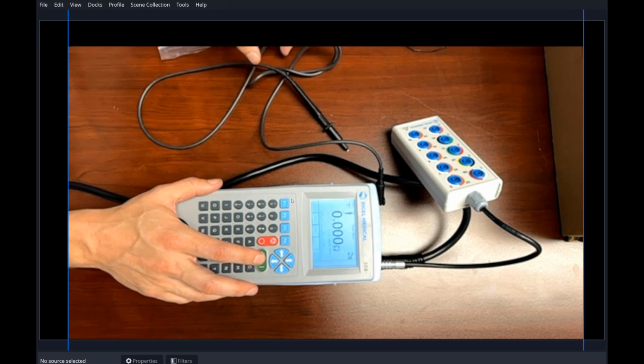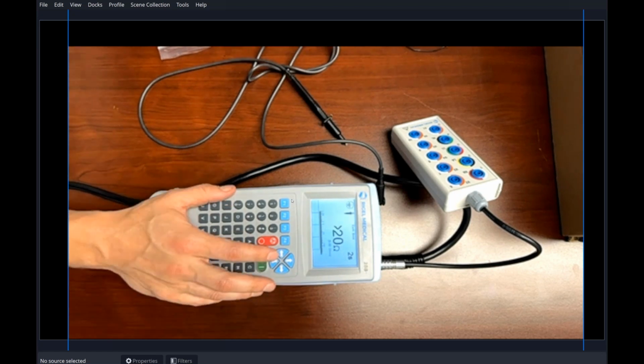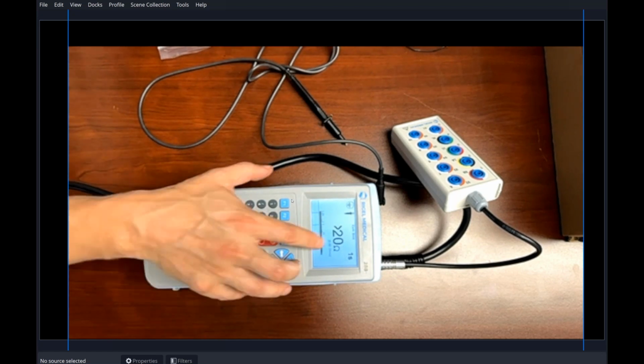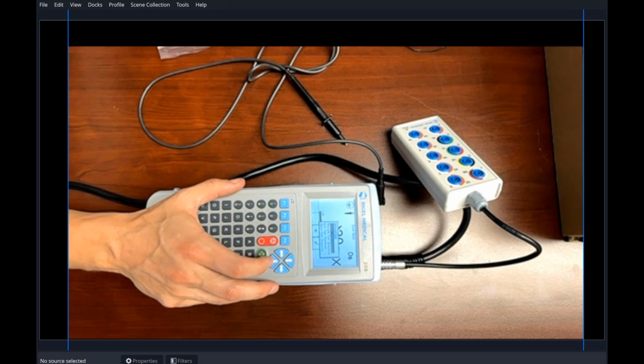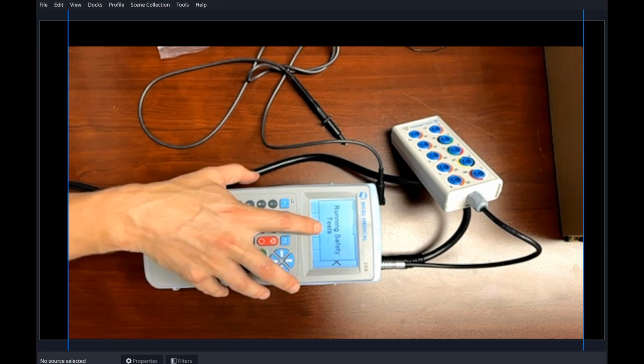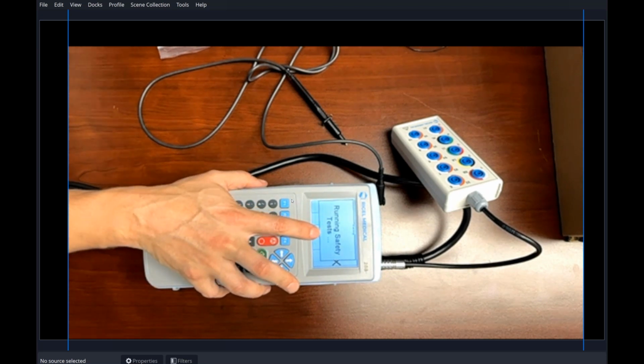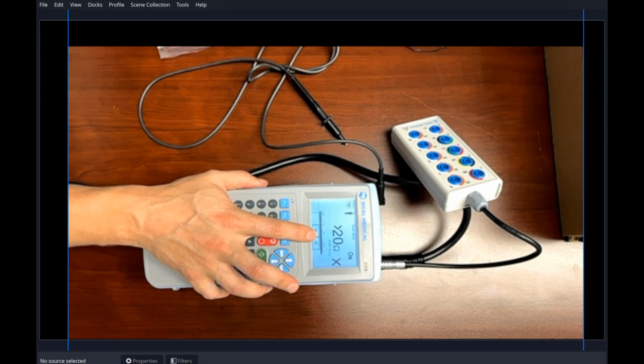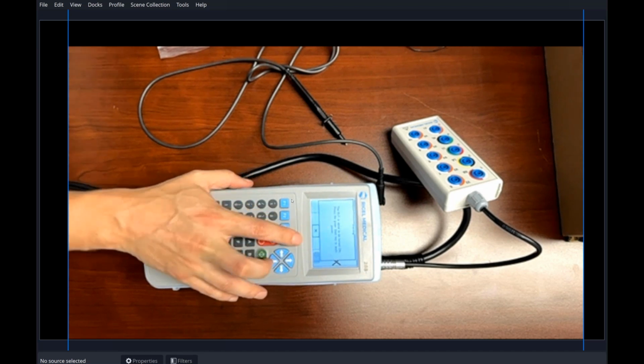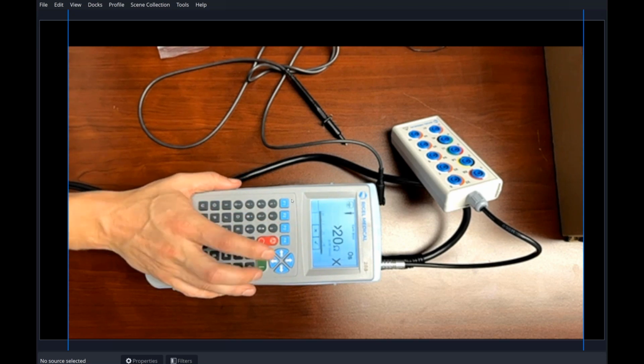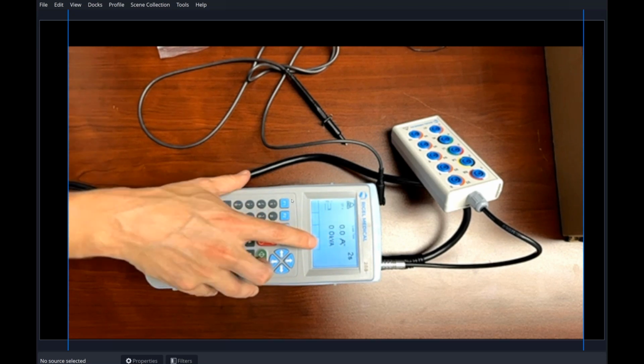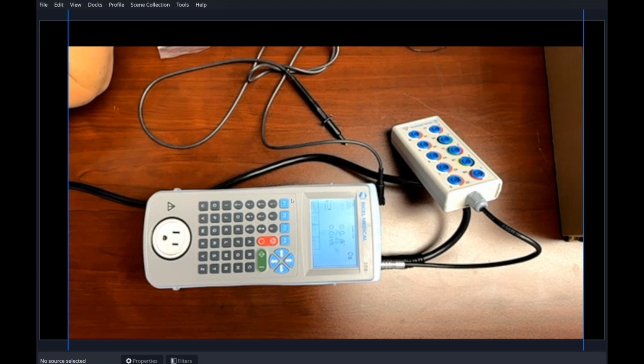And then it's a case of just following the sequence of events. This one will fail because it's not connected to any device right now. Press key to start, and then it will continue to run through the test until the end. So the ET should be turned on. Press the green key to start, and it will give you a series of tests which will run through automatically. And each time that it does that, you just hit the green button, and it will run through as a sequence right until the end.